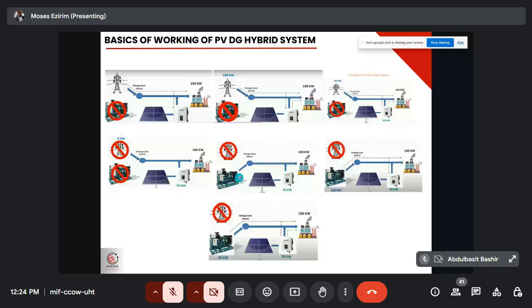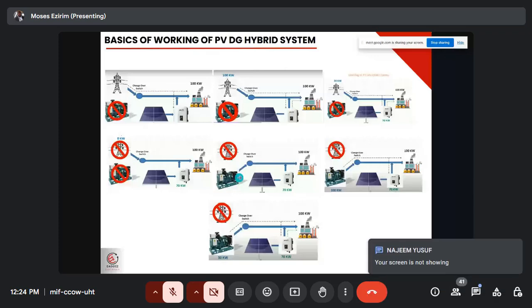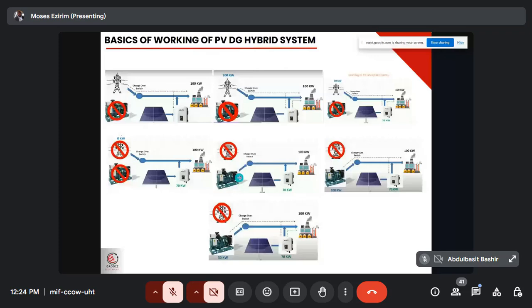Generator comes up. I supplied the 100, supply the whole 100. Once the generator has come up, they do not change from the generator if it can sync. If they have the same voltage, the same frequency, the same phase, then it can now start discharging its own power.